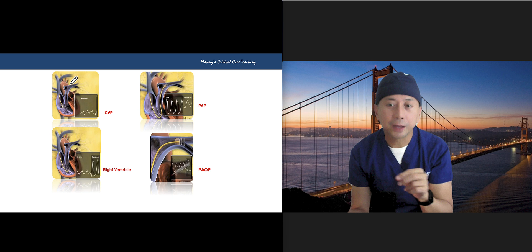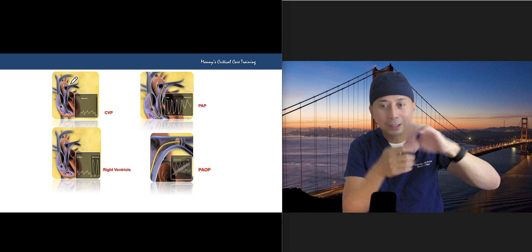So some ICUs have those 1 bag, 3 pressure transducers, right? So you get your normal saline, depending on how active and your protocol. Some of the ICUs only use 500. Some ICUs use 1,000. So depending on what your guidelines are, let's just say you use 500. So some nurses will poke the saline, like remove the seal, poke it and remove it. Make sure you keep the sterility, and you burp, right? You burp your saline, getting rid of the air, and as you are burping it, you poke it again and keep it up, right? Keep it on there, right?